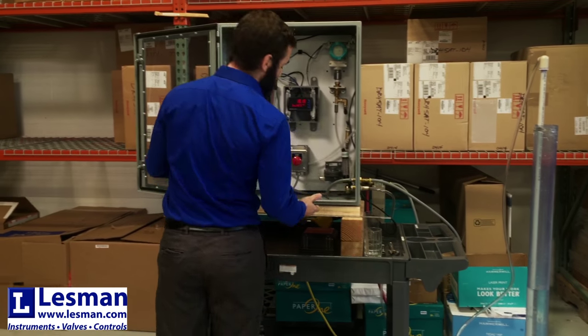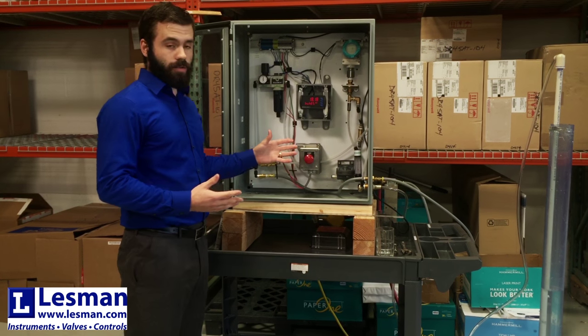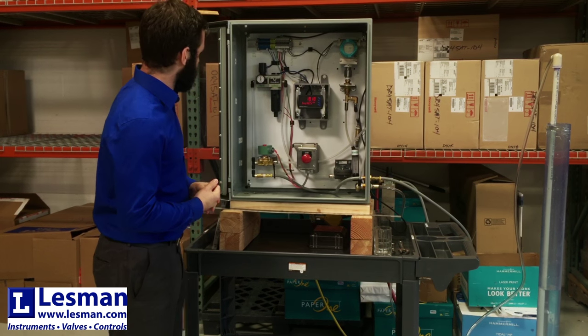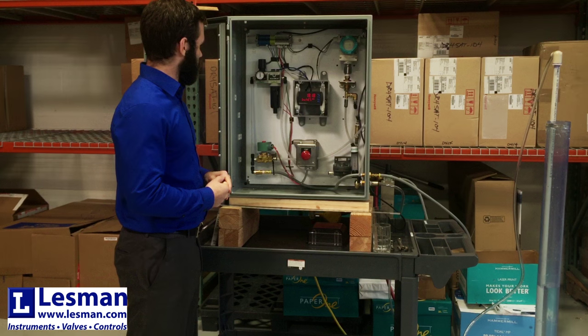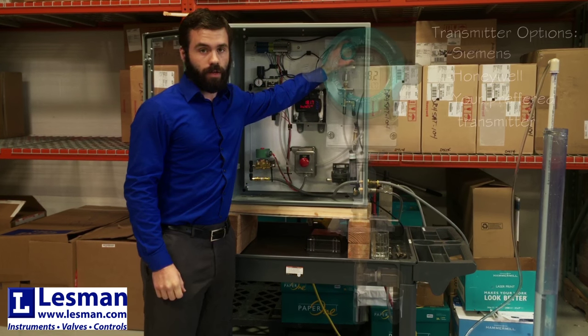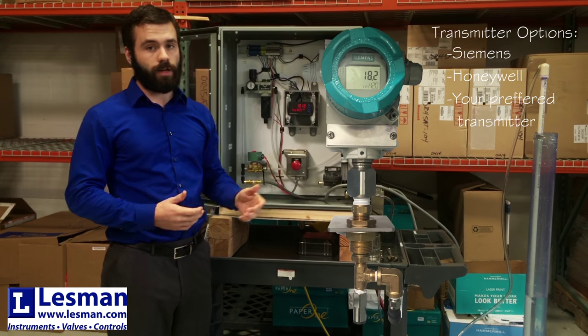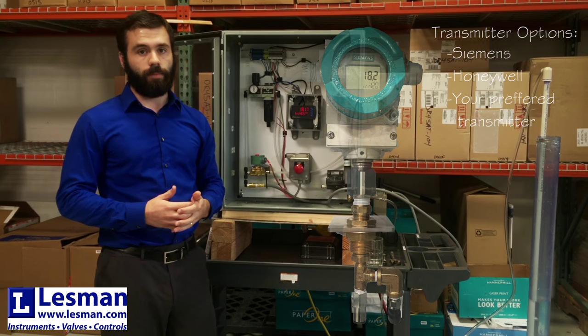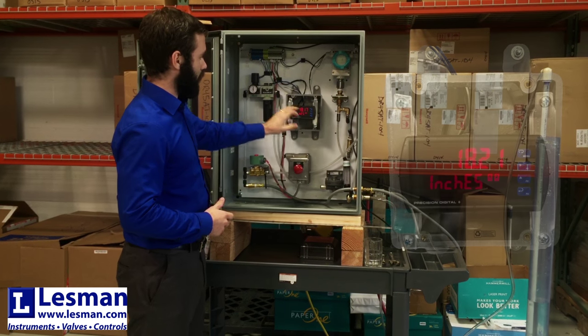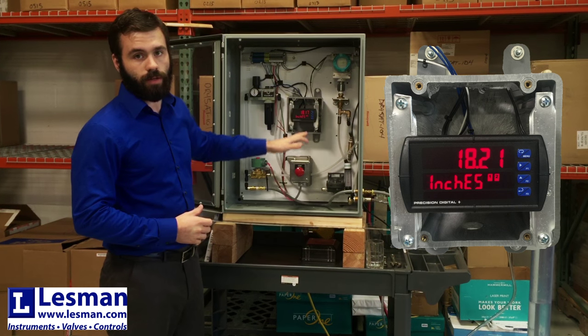That's the basic concept and the whole theory behind what a bubbler does. Ours in particular uses the Siemens constant differential relay and pneumatics for our regulator and filter. For the transmitter, we can use whatever you want — we use Siemens and Honeywell generally, but we've had Rosemount and Foxboro come in as well. It's very customized. Right now we're using a precision digital display with nice big lettering that can tell you the level in inches, feet, whatever you want.